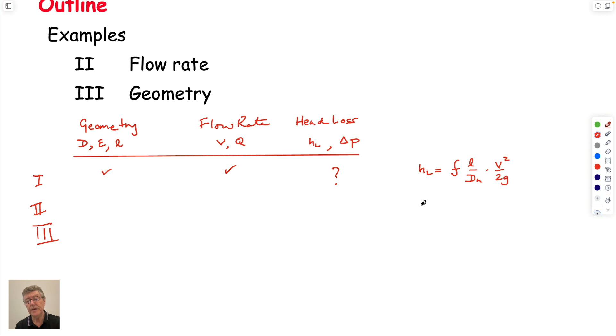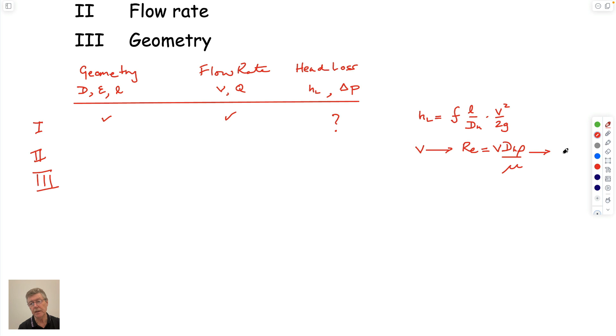So v is used to calculate a Reynolds number, which is equal to velocity times characteristic dimension times density over viscosity. And we use that to calculate friction factor. And we use that to calculate head loss, pretty straightforwardly. So everything's preordained: you know the geometries, you know all the characteristics of the system, you know all the geometric components, and you know velocity. So as a function of this, you can calculate from a velocity, diameter, density, and viscosity a friction factor, and then use that to calculate head loss.